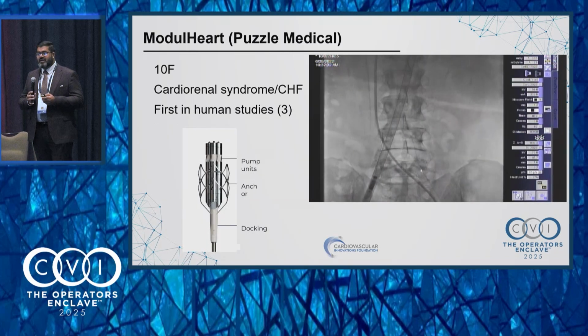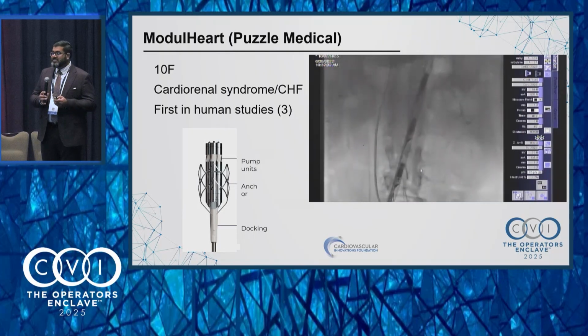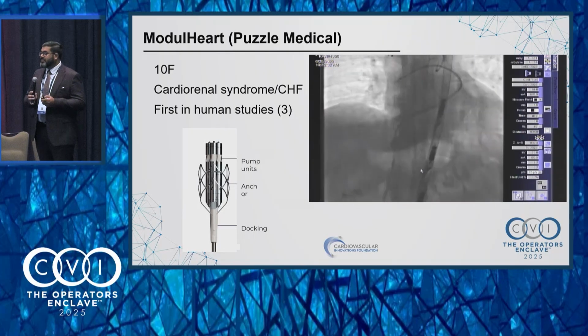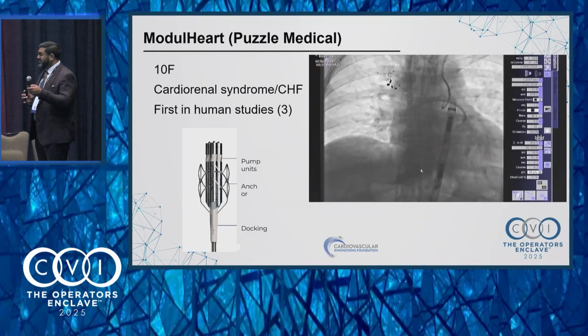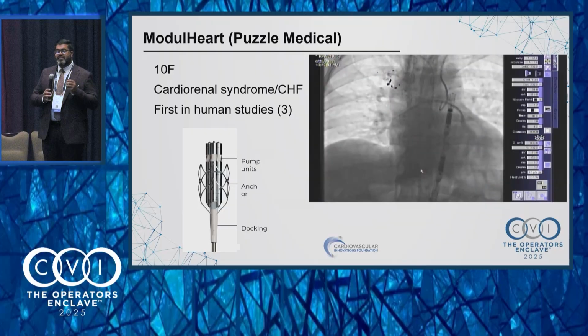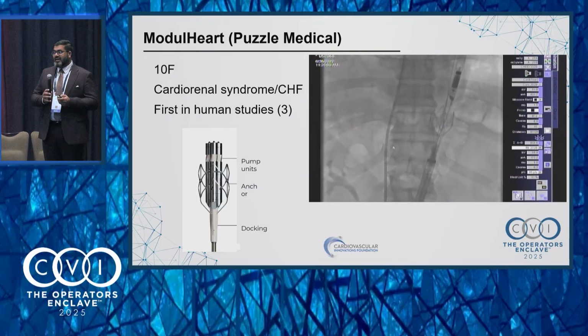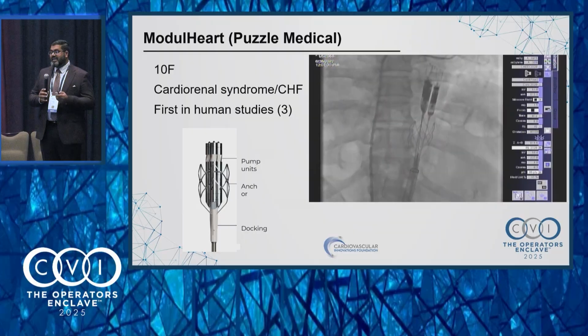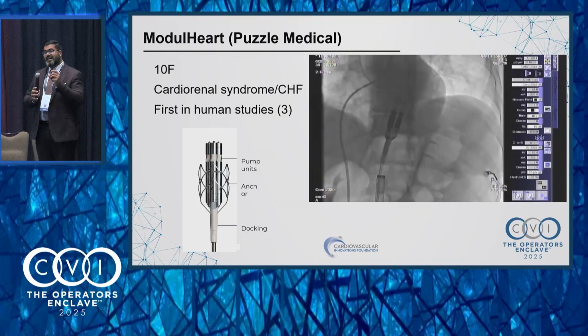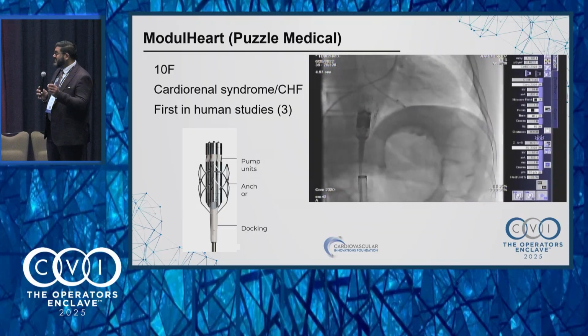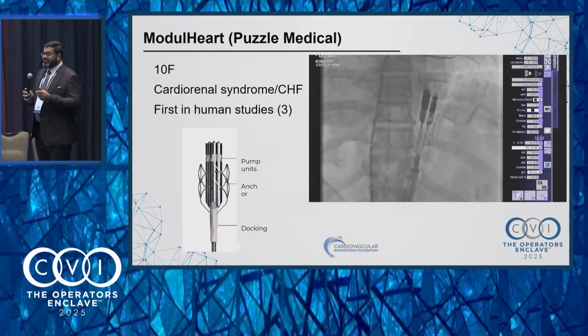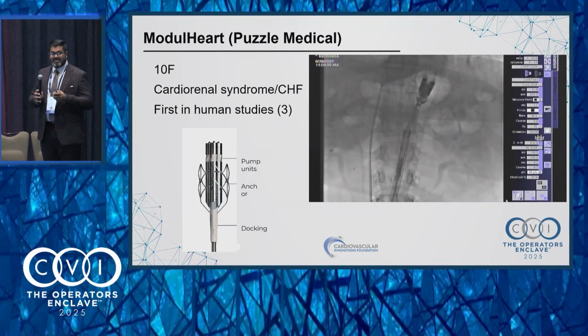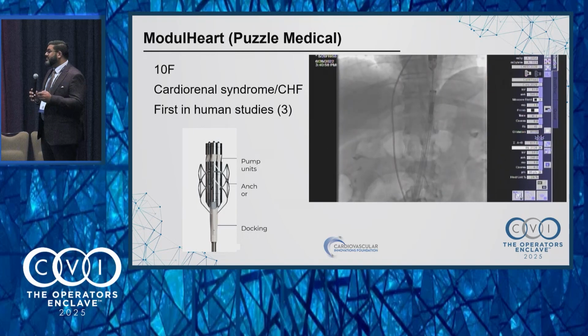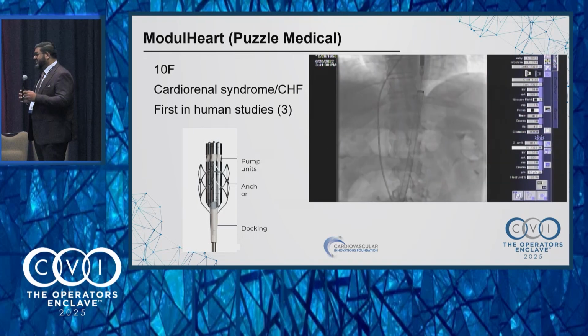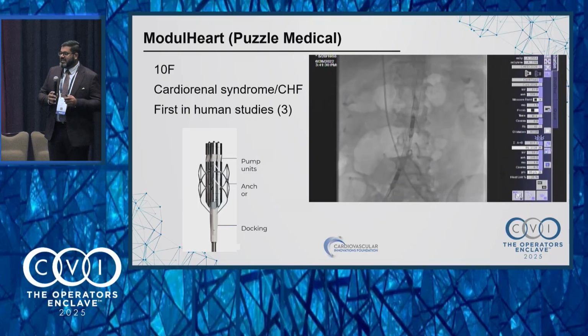And a similar device is the Puzzle Medical system device that can be put in through a 10 French sheath. The case example I'm showing you is through a 14 French sheath. It's also a cardiorenal device. They've done 3 first-in-human cases in Georgia, and it can basically have multiple devices within the descending aorta and provide anywhere from 6 to 10 liters of flow. So even though it's not purposefully built for cardiogenic shock, you can imagine the opportunities that potentially are there.